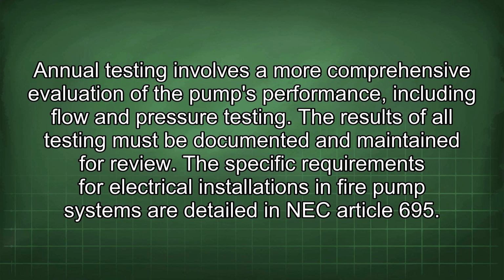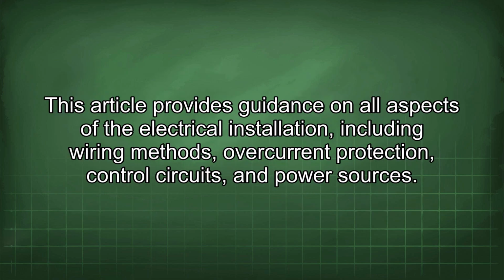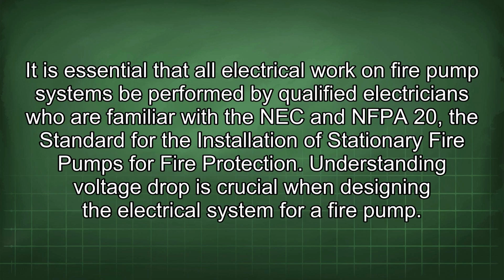The results of all testing must be documented and maintained for review. The specific requirements for electrical installations in fire pump systems are detailed in NEC Article 695. This article provides guidance on all aspects of the electrical installation, including wiring methods, overcurrent protection, control circuits, and power sources. It is essential that all electrical work on fire pump systems be performed by qualified electricians who are familiar with the NEC and NFPA 20, the standard for the installation of stationary fire pumps for fire protection.